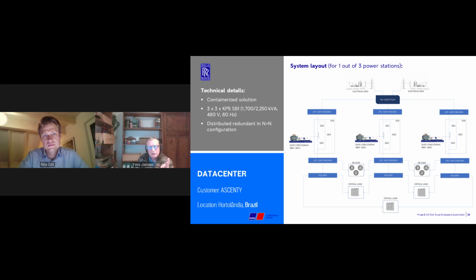As mentioned, all the MTU kinetic power packs are installed in containers outside the data center. So it's a dual output dynamic UPS. What is a dual output dynamic UPS? It's a system capable of protecting two types of loads: the critical loads that require high quality power supply, and essential loads that can accept an outage for a maximum of 15 seconds.